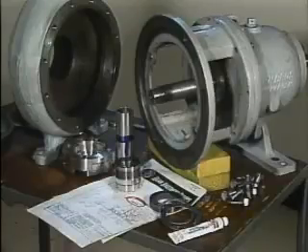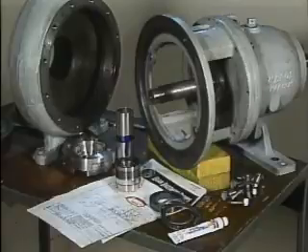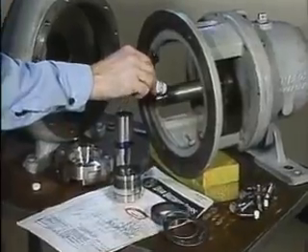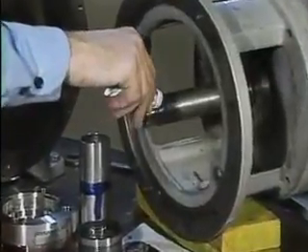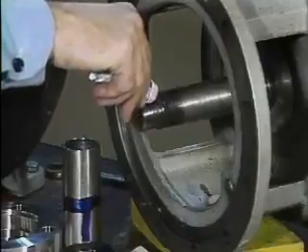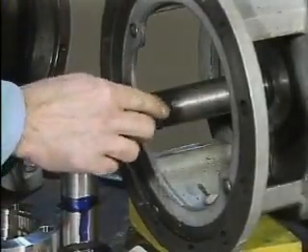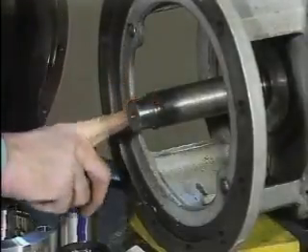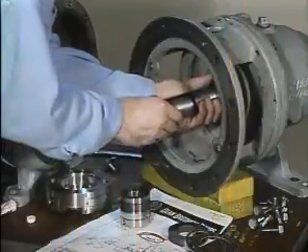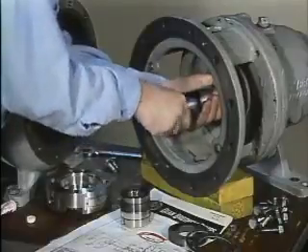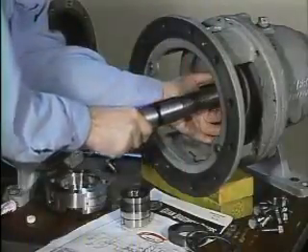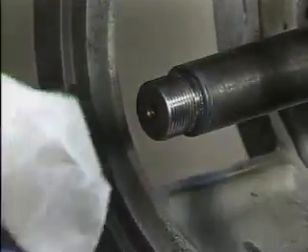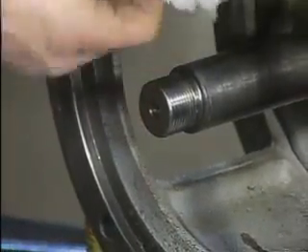But some pumps rely on metal-to-metal contact instead of a gasket or an O-ring to seal between the shaft shoulder and the sleeve. On these pumps, the surfaces should be lapped to remove imperfections that could interfere with creating an acceptable seal. To do this, the shaft key is removed and then lapping compound is applied to the shaft shoulder. Next, the sleeve is placed on the shaft and turned. After several minutes, the sleeve is taken off, and the lapping compound is cleaned away. The surfaces are then inspected to make sure that proper surface contact can be made.